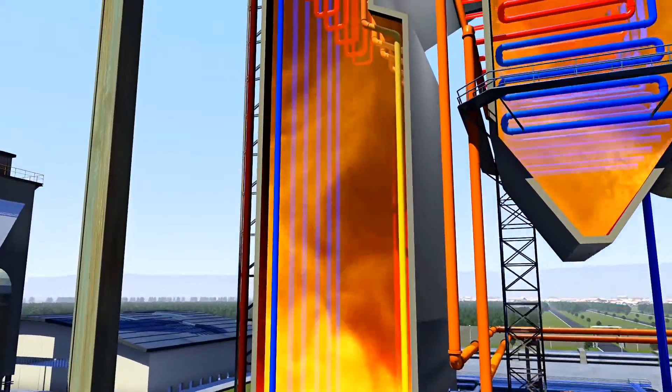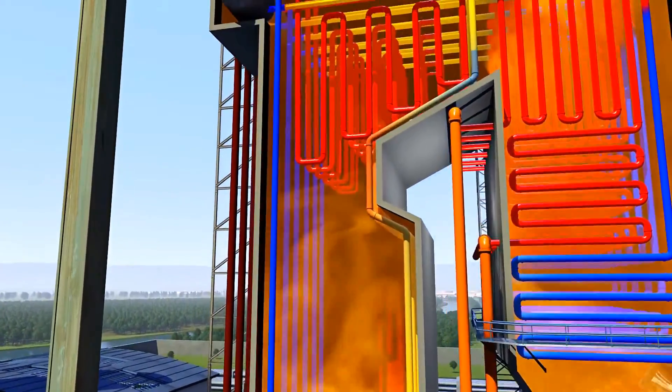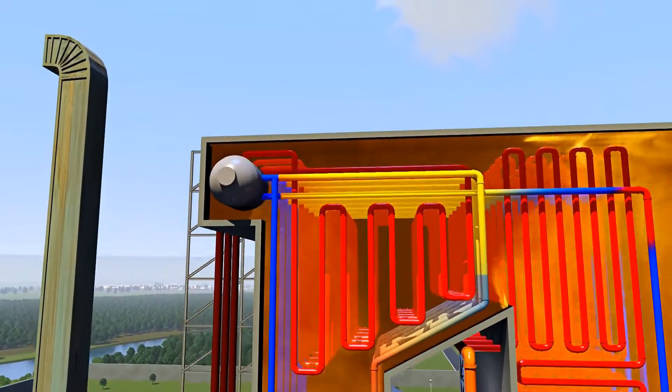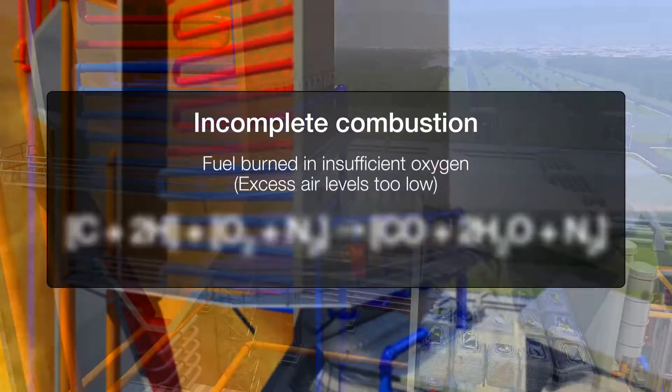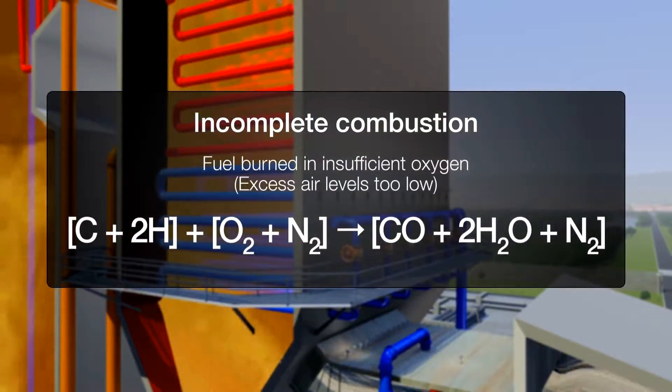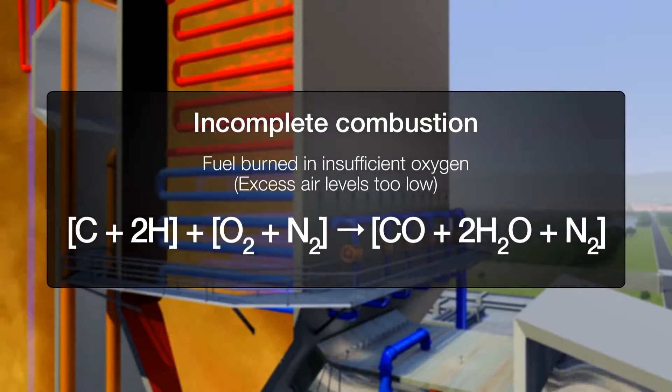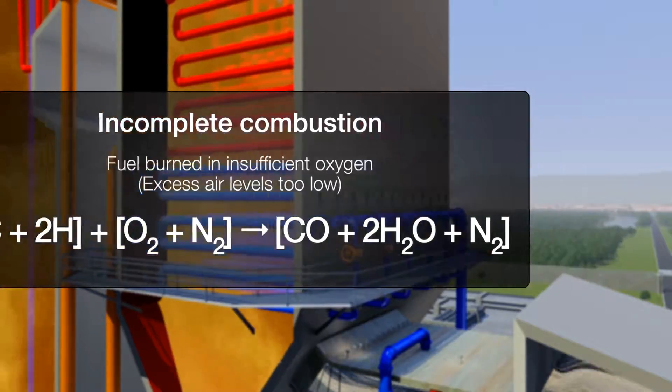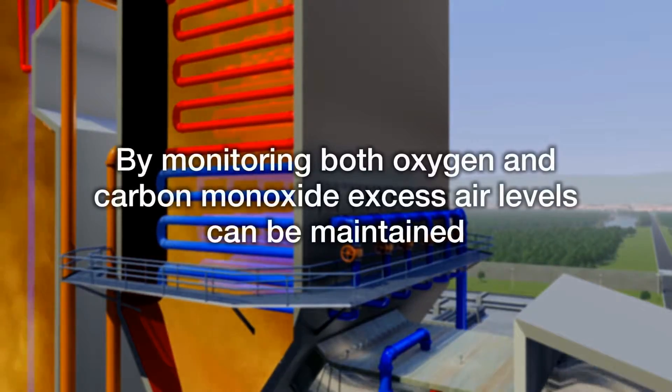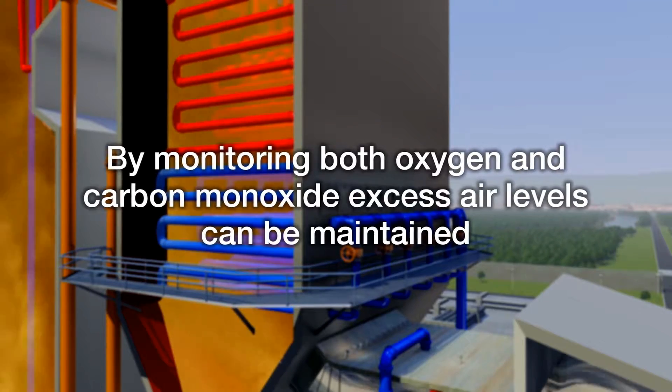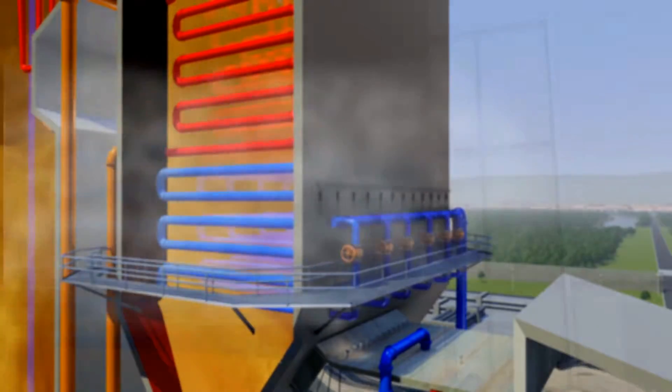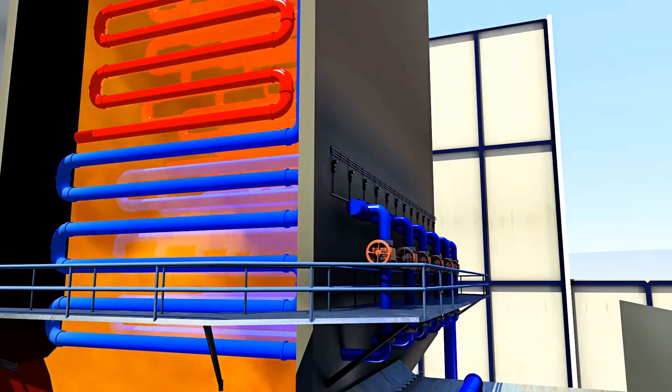Measuring for carbon monoxide provides an ideal means of compensating for these variations. Carbon monoxide levels will start to increase when the amount of oxygen is insufficient to allow complete combustion. By continuously balancing the two measurements against each other, it's possible to achieve and maintain the correct amount of excess air for optimum combustion, regardless of any of the variations mentioned earlier.